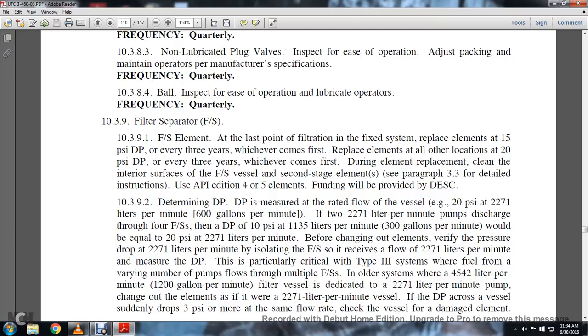10.3.9.2 On determining the DP: the DP is the pressure at the rated flow of the vessel at 600 gallons per minute, or 2 pumps at 600 gallons per minute discharging through 4 filter separators. Then a DP of 10 psi at 300 gallons per minute would be equal to 20 psi at 600 gallons per minute. But before changing an element, verify the pressure drop at 300 gallons per minute.